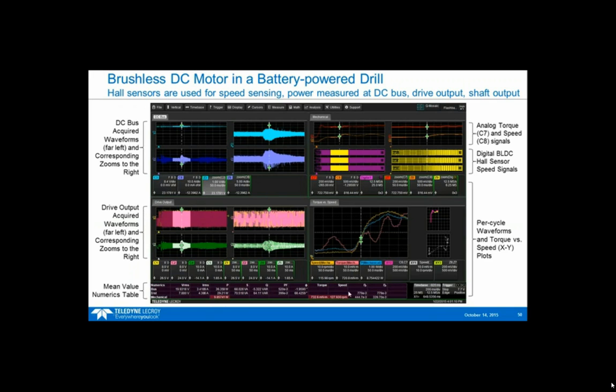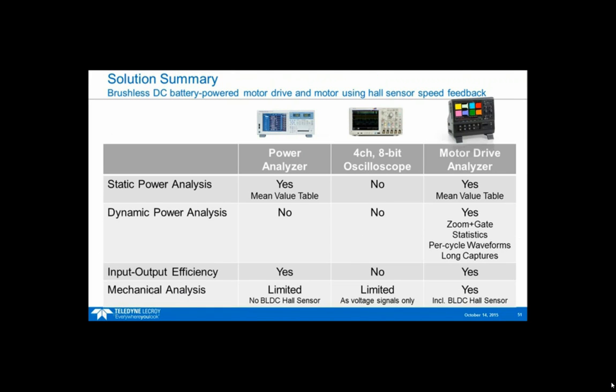This is the mean value table, and we're plotting 3 things over time: the speed, the torque, and the power. And so you can see how that's changing. And also we have some XY plots here to show torque versus speed characteristics. So this is an interesting example, and primarily it shows the capability we have in the motor drive analyzer to provide a very comprehensive set of mechanical analysis tools, primarily because we can integrate brushless DC Hall sensors for speed, but also quadrature encoders and resolvers as well.